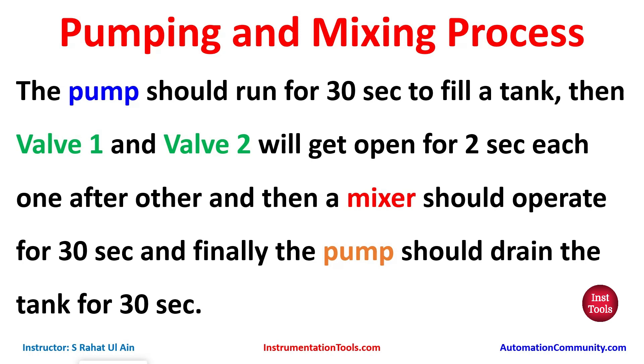We will use a normally closed contact and some timers. For the first pump we will use a Time Pulse (TP) that will run for 30 seconds. For valve 1 and valve 2 we will use an on-delay timer (TON) and also a time pulse. For the mixer we will use both on-delay timer and time pulse, and for the second pump we will also use on-delay timer and time pulse.